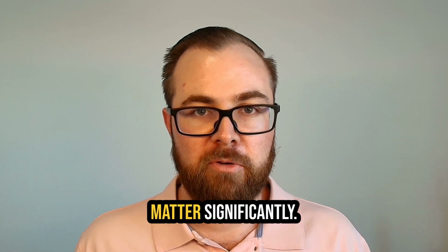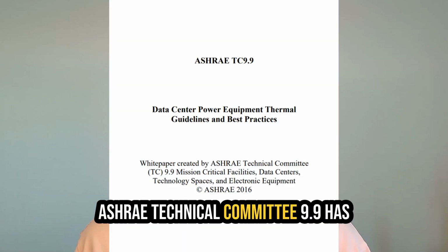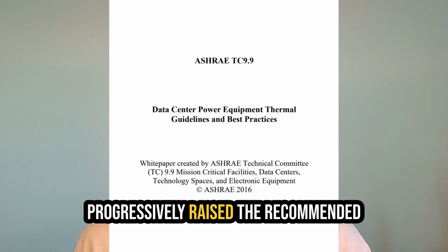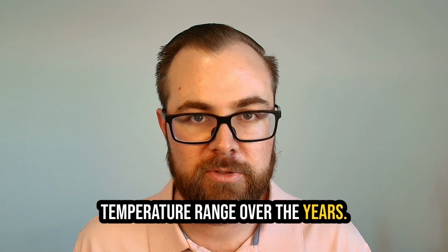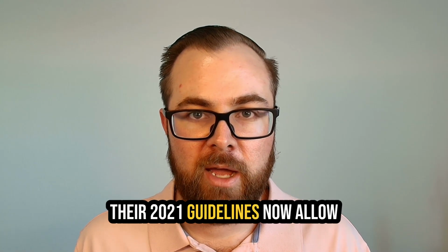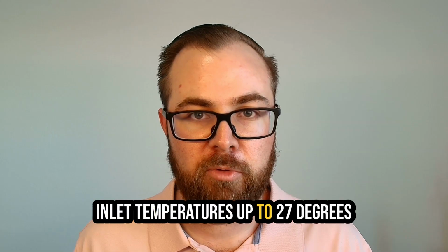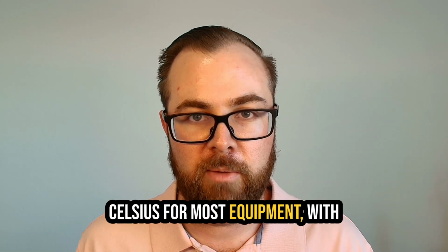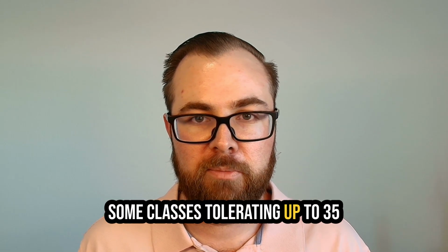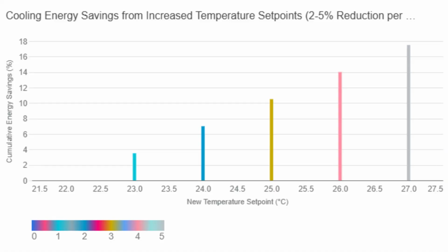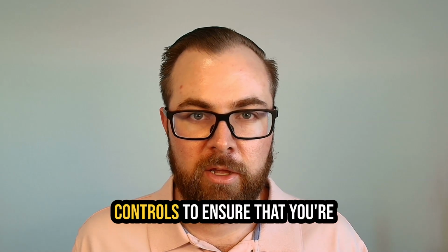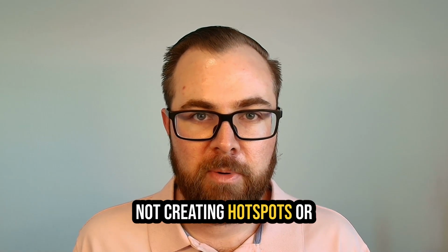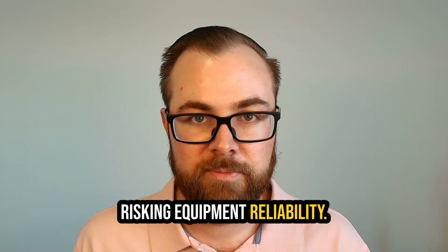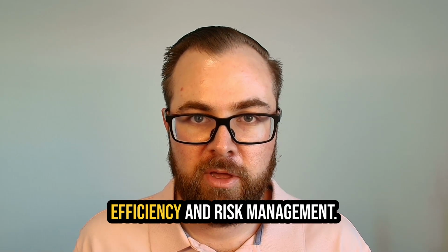Temperature set points matter significantly. ASHRAE Technical Committee 9.9 has progressively raised the recommended temperature range over the years. Their 2021 guidelines now allow inlet temperatures up to 27 degrees Celsius for most equipment, with some classes tolerating up to 35 degrees. Every degree you raise the set point reduces cooling energy by approximately 2 to 5%. But you need monitoring and controls to ensure that you're not creating hotspots or risking equipment reliability. It's a balance between efficiency and risk management.